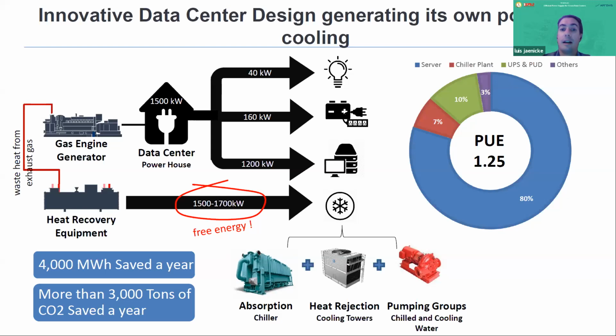Remember, in the previous scenario, we were importing 2 megawatts from the grid. Now I need to produce at site 1.5. So there is a half a megawatt or 500 kilowatt reduction in power to this data center. And of course, that has a huge impact on the PUE, the power use effectiveness of the data center. Previous value was 1.67, and with a cogeneration or combined power and cooling, my PUE value drops to 1.25.